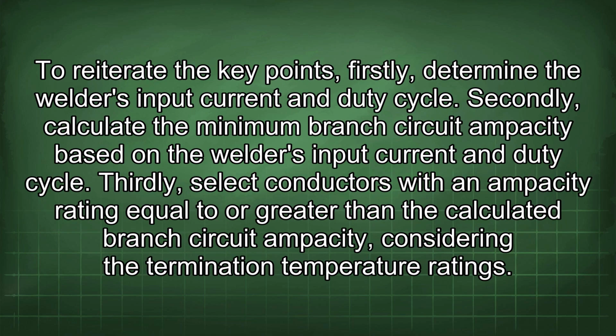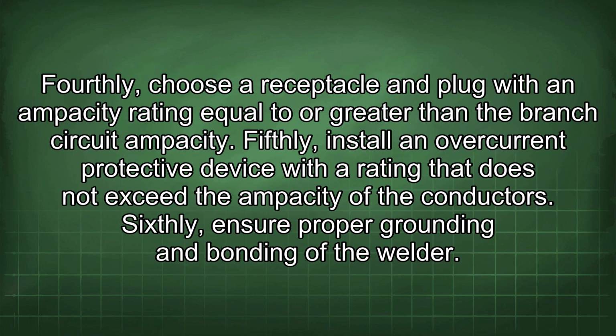To reiterate the key points, firstly, determine the welder's input current and duty cycle. Secondly, calculate the minimum branch circuit ampacity based on the welder's input current and duty cycle. Thirdly, select conductors with an ampacity rating equal to or greater than the calculated branch circuit ampacity, considering the termination temperature ratings. Fourthly, choose a receptacle and plug with an ampacity rating equal to or greater than the branch circuit ampacity. Fifthly, install an overcurrent protective device with a rating that does not exceed the ampacity of the conductors. Sixthly, ensure proper grounding and bonding of the welder.